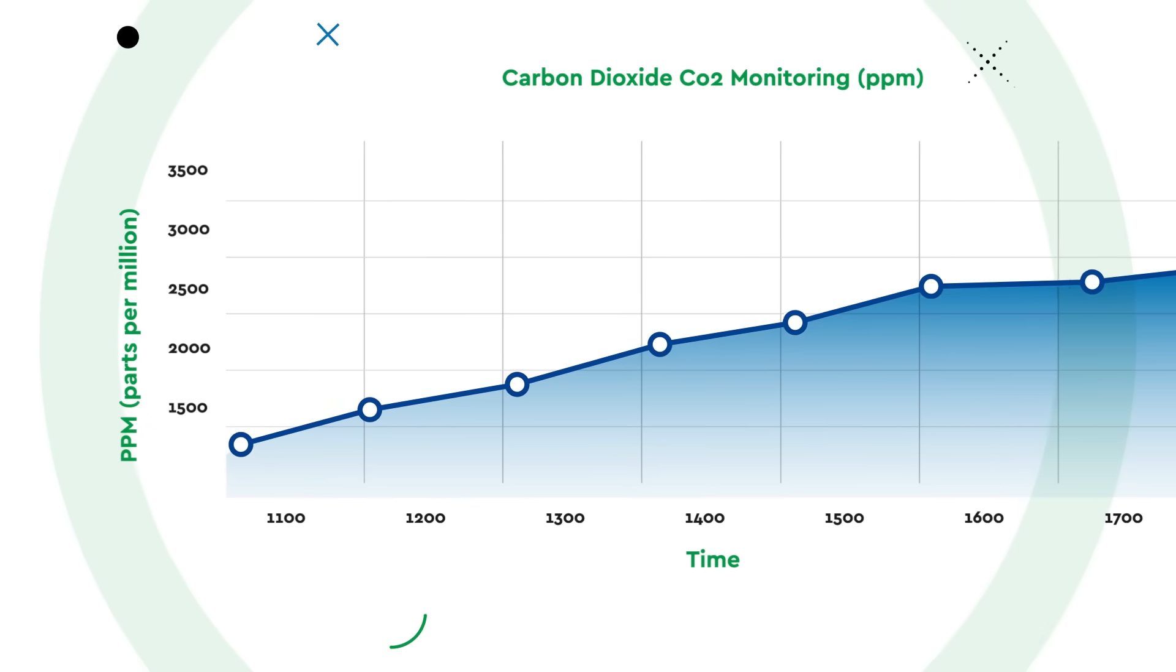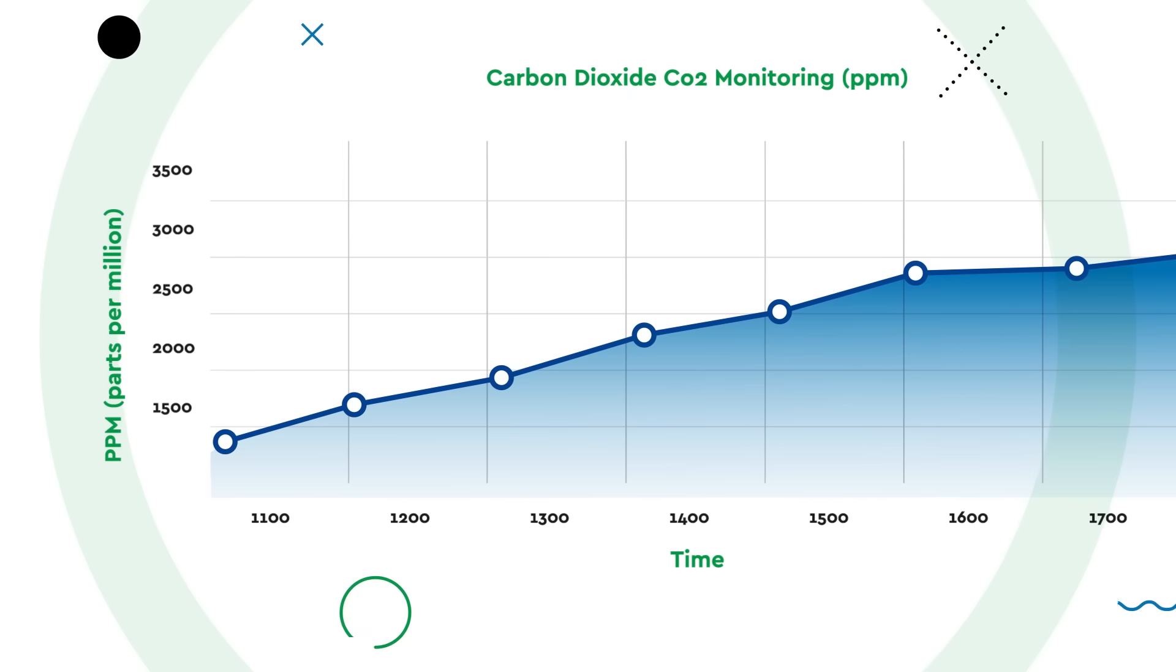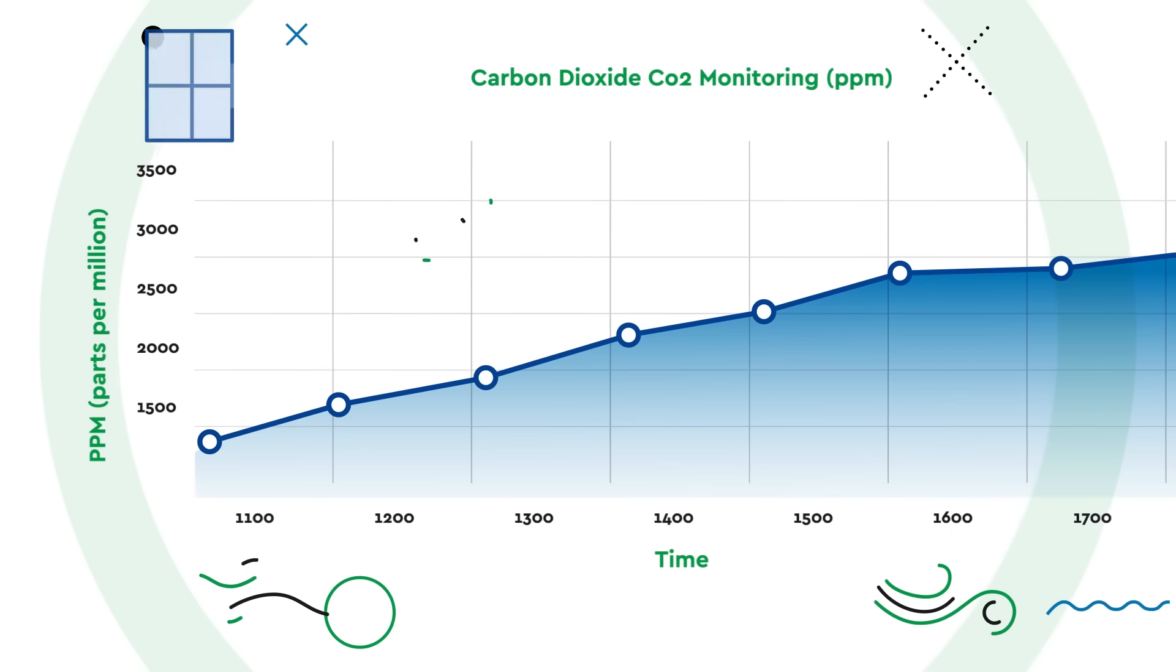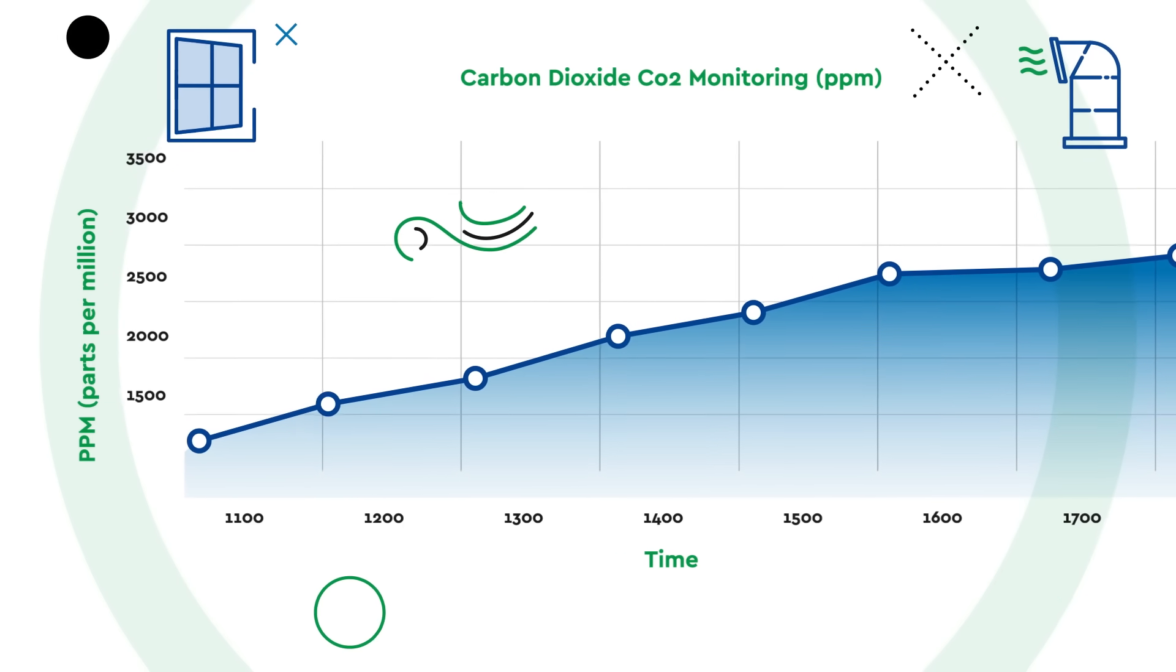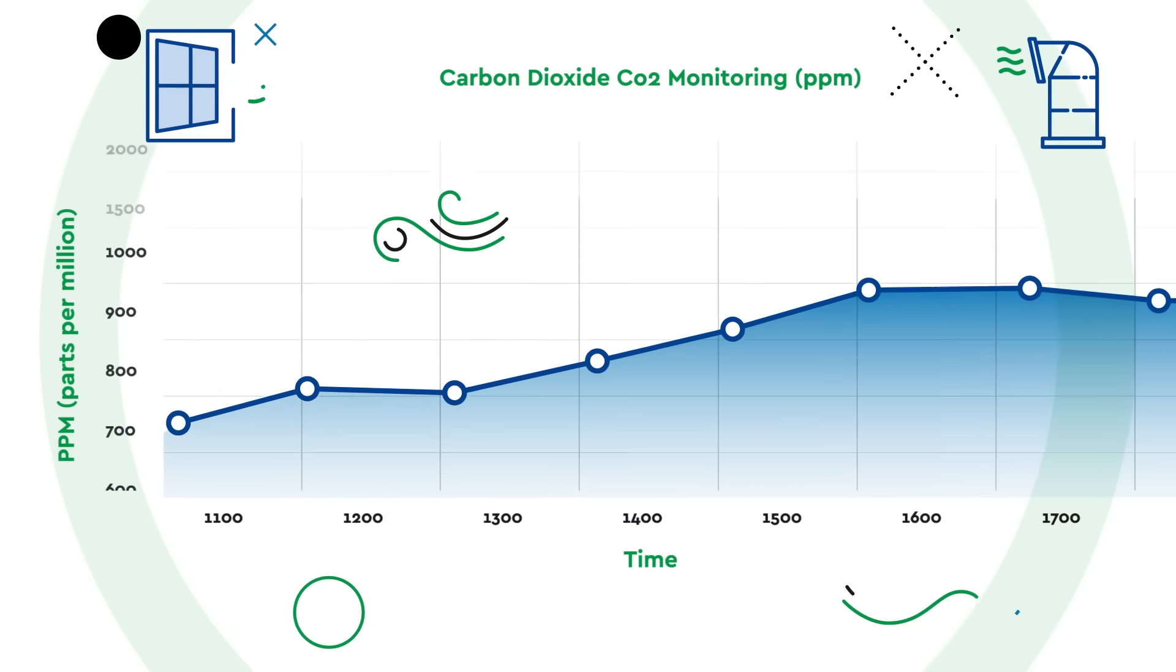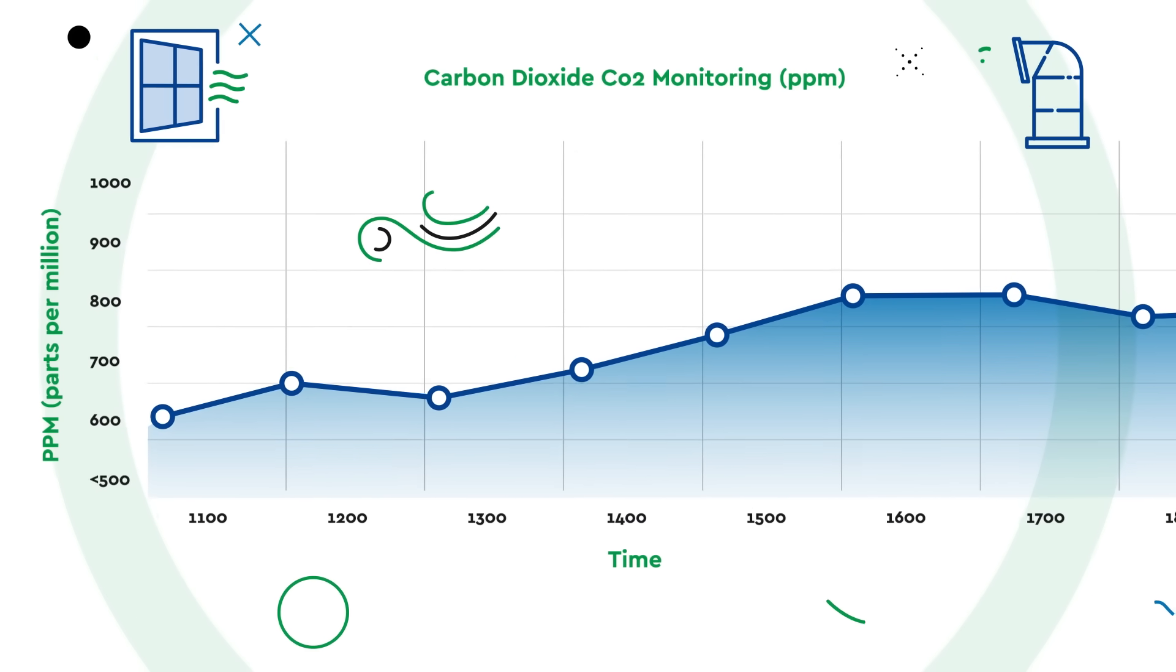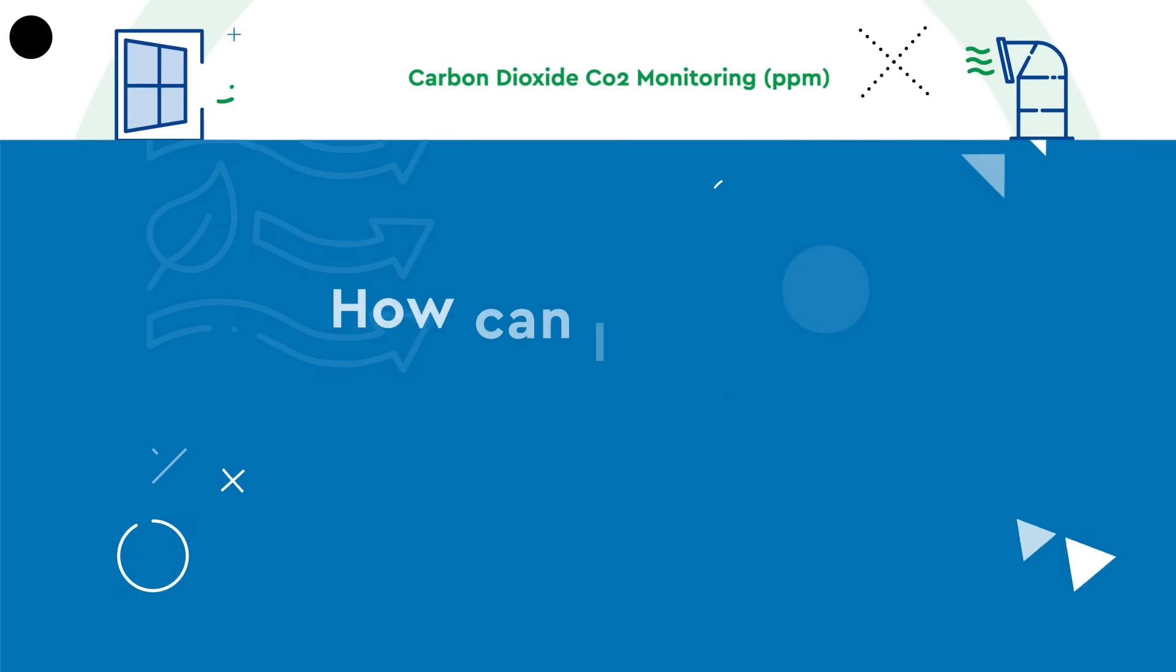Good indoor air quality, managed with an efficient ventilation system using the correct ratio of fresh to recirculated air, should achieve carbon dioxide levels below 1,000 parts per million.